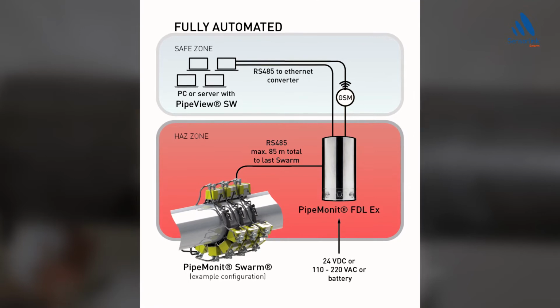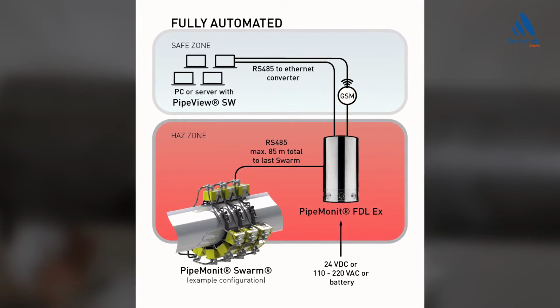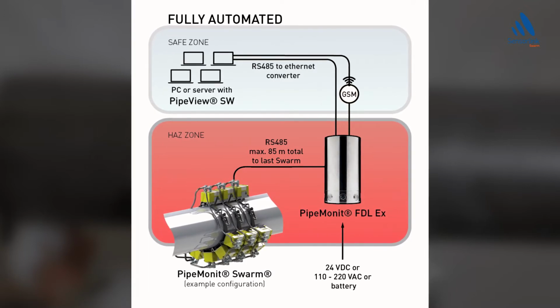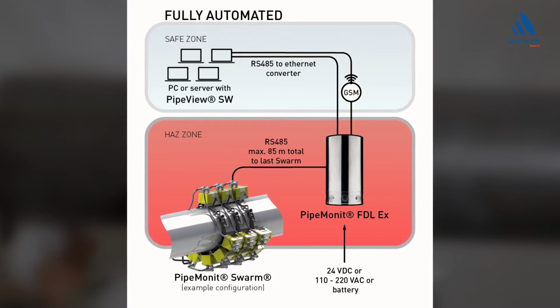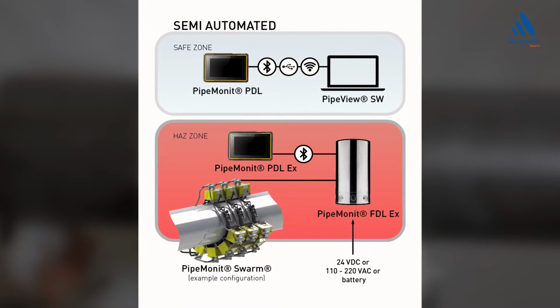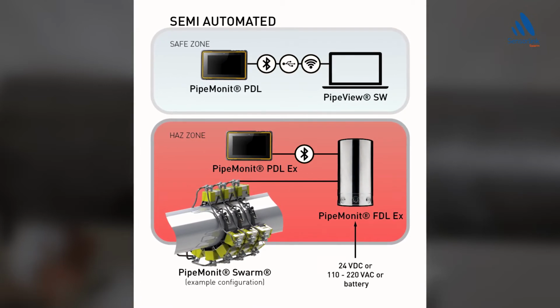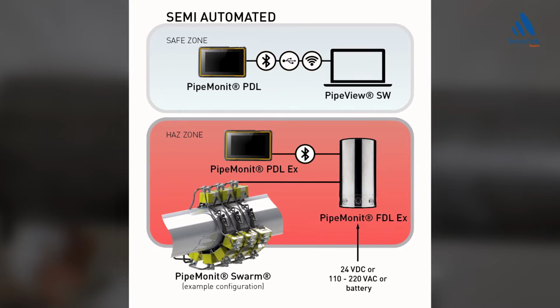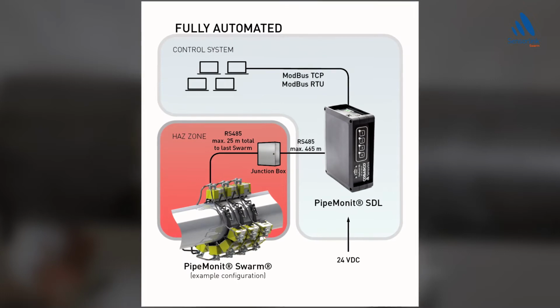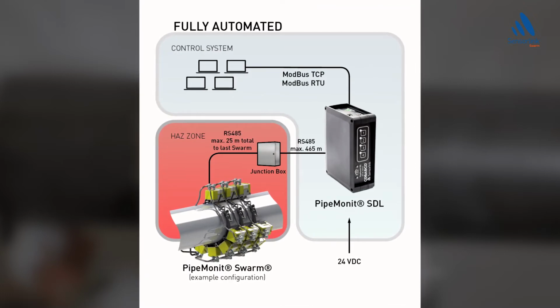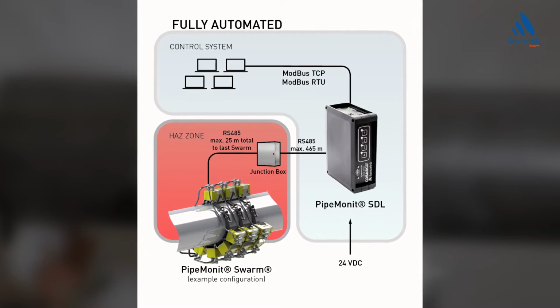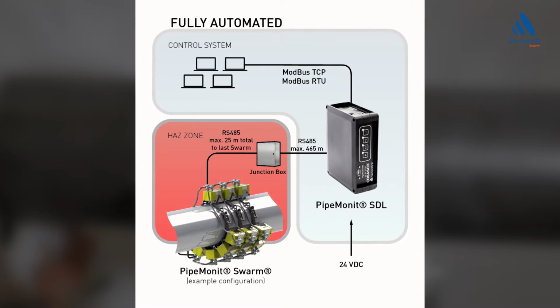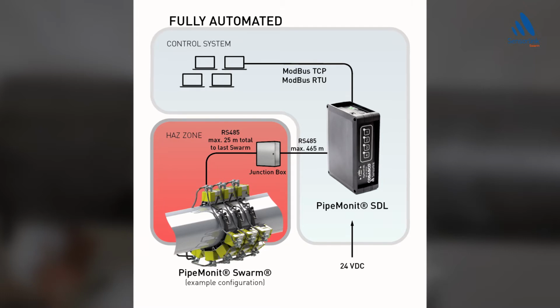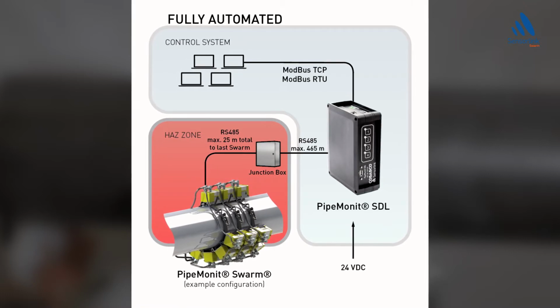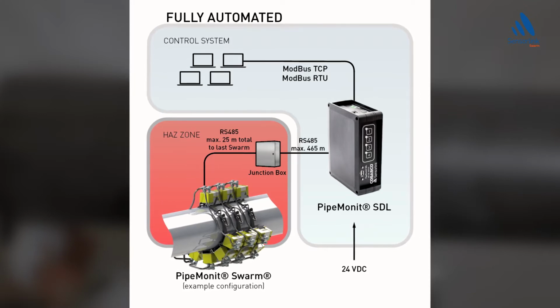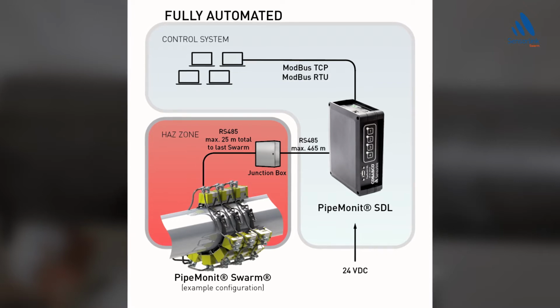The Pipe Monit Swarm system can be delivered with different data logger options. The FDL-EX data logger can be installed in EX zones and is delivered with a GSM modem for wireless operation. Semi-automatic option is also available, where the FDL-EX logs data continuously and data can be collected at any time using the Bluetooth connection. The SDL data logger is installed in safe zone, while the sensors are installed in the hazardous zone. The SDL is cabled to the sensors in the hazardous zone, and the communication interfaces to the control system are either Modbus TCP, Modbus RTU, or OPC. We also have the option of installing the SDL in the hazardous zone. This is called SDL-EX.